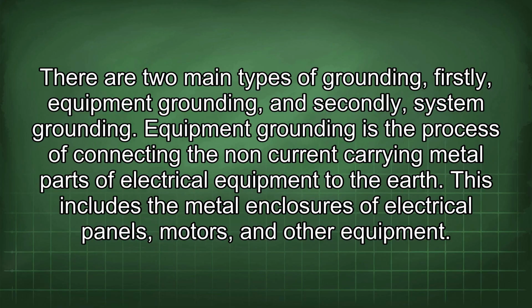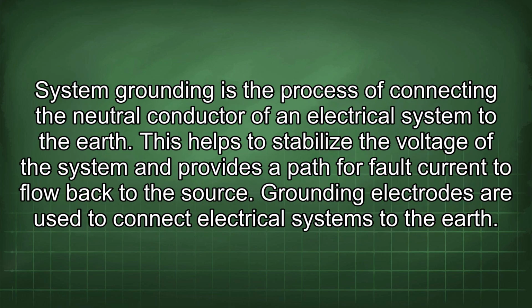Equipment grounding is the process of connecting the non-current carrying metal parts of electrical equipment to the earth. This includes the metal enclosures of electrical panels, motors, and other equipment. System grounding is the process of connecting the neutral conductor of an electrical system to the earth. This helps to stabilize the voltage of the system and provides a path for fault current to flow back to the source. Grounding electrodes are used to connect electrical systems to the earth.